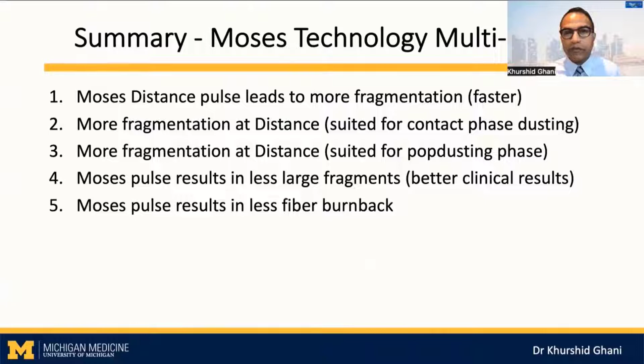Moses pulse results in less large fragments, and this would mean better clinical results, because as we know, fragments that are larger than 2 millimeter in size are the ones that cause problems in terms of reintervention. And the other striking finding on using multipulse is the protection on laser fiber burnback. And we know if we can prevent this, this will also lead to an improvement in fragmentation. So altogether, all these factors improve the efficiency of laser lithotripsy.